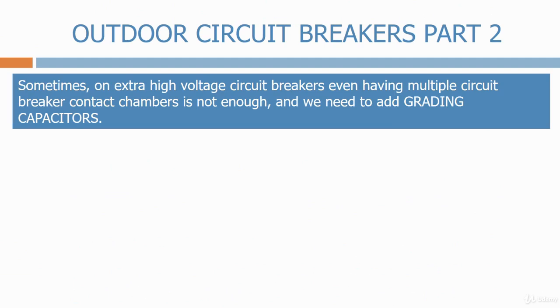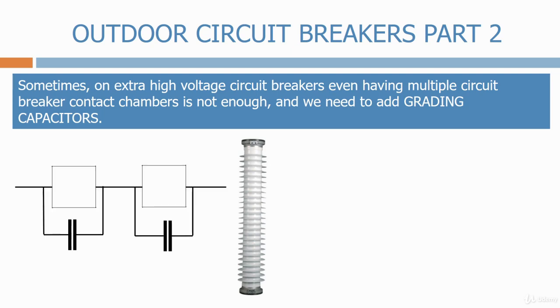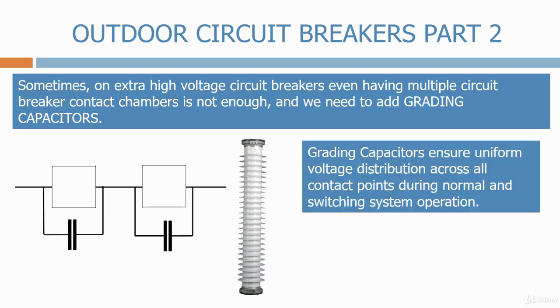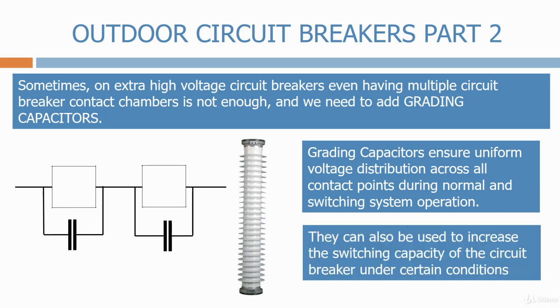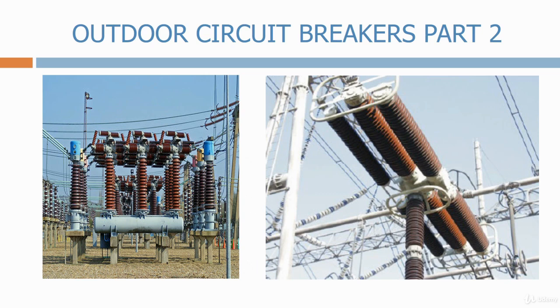Sometimes, on extra high voltage circuit breakers, even having multiple circuit breaker contact chambers is not enough, and we need to add grading capacitors. These are positioned in parallel with all the circuit breaker contacts. Grading capacitors ensure uniform voltage distribution across all contact points during normal and switching system operation. They can also be used to increase the switching capacity of the circuit breaker under certain conditions. Here we have some typical examples of grading capacitors on some high voltage circuit breakers.